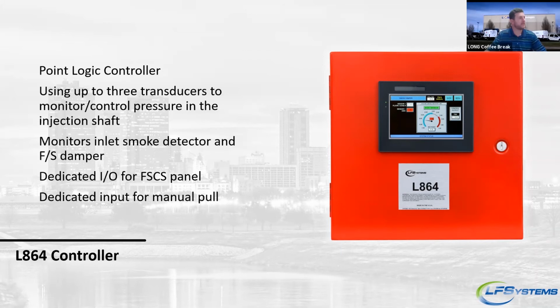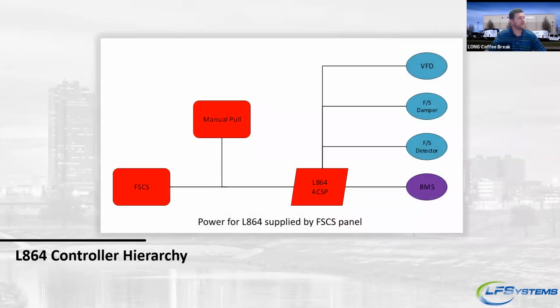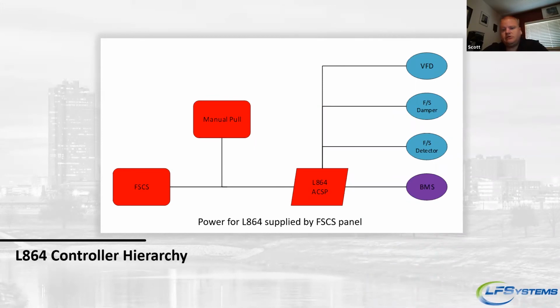Pretty slick. Let's take a look at the hierarchy of the 864. As you can see here, the FSCS or the manual pull will activate the 864. The 864 will then control the VFD. It will also control and monitor the fire smoke damper and fire smoke detector on the inlet of the fan to prevent smoke from circulating back into the stairwell. And it can also feed all this information to the BMS either via BACnet or LON.